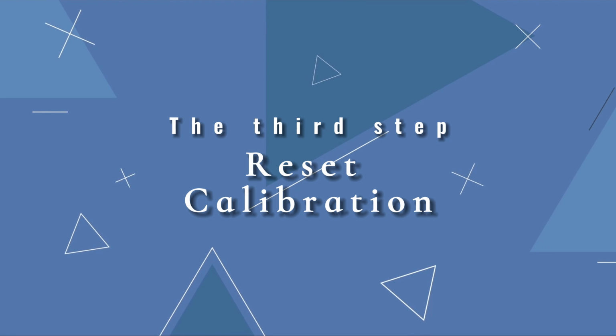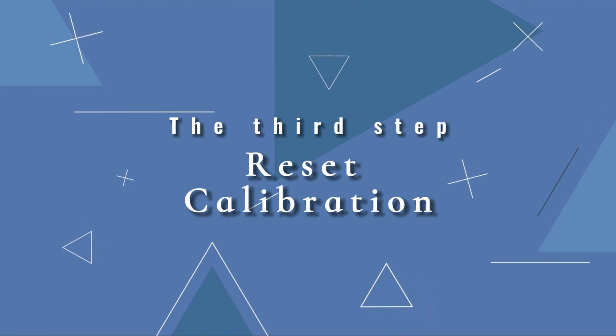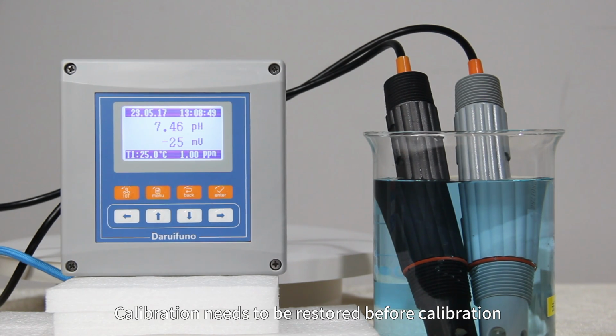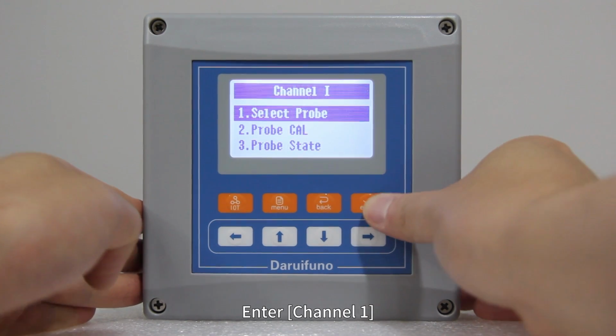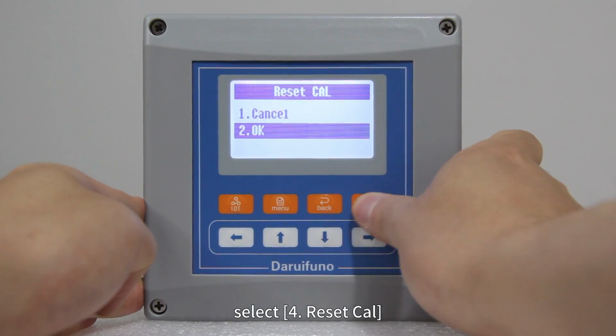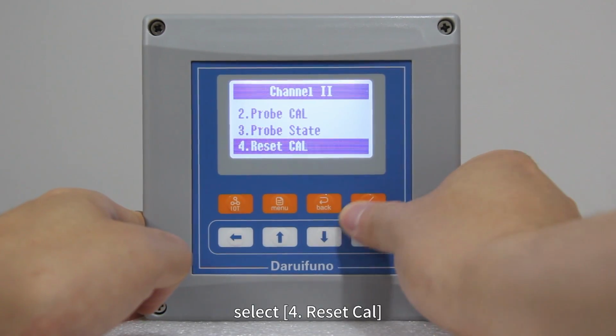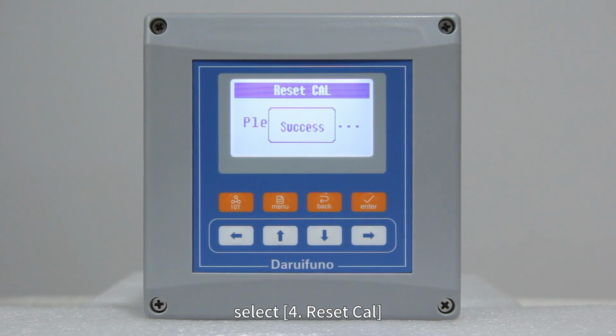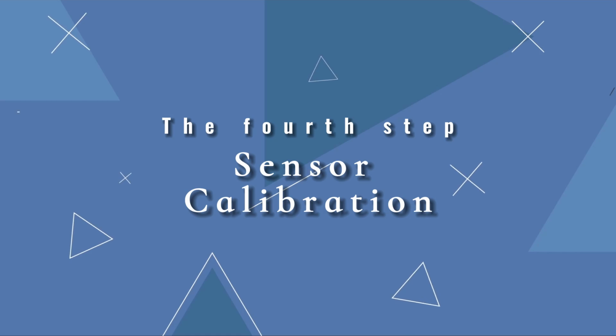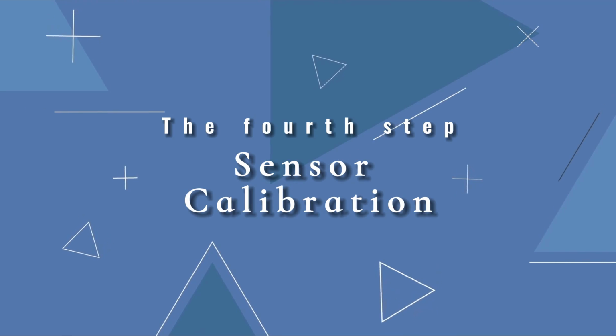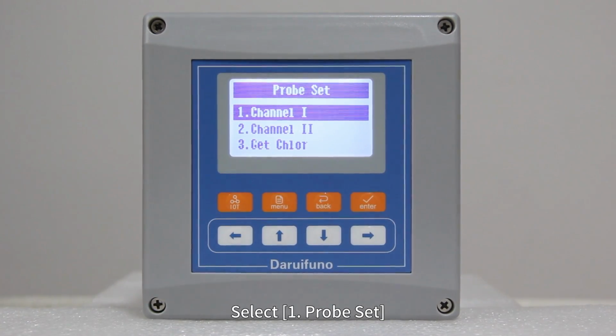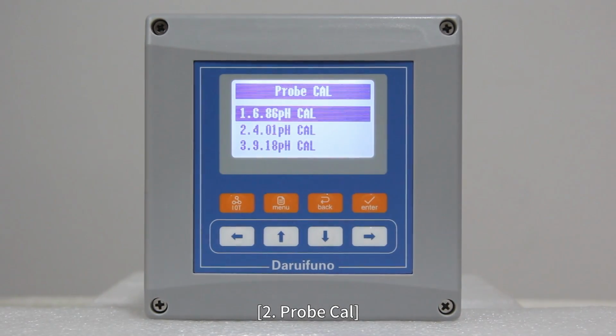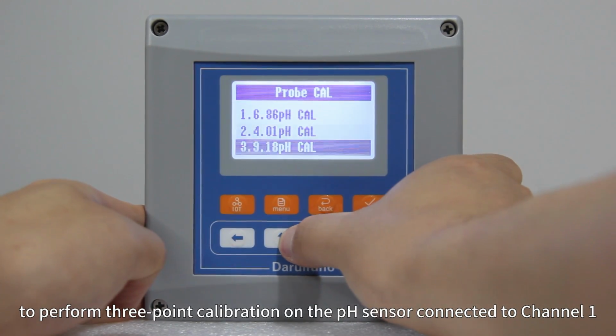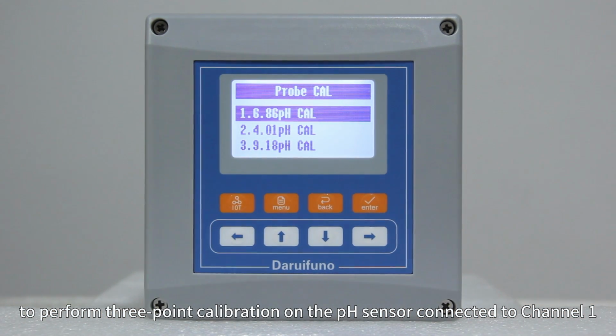The third step, reset calibration. Calibration needs to be restored before calibration. Enter Channel 1. Select Fourth, Reset Cal, and confirm. Enter Channel 2. Select Fourth, Reset Cal, and confirm. The fourth step, sensor calibration. Select First Probe Set, First Channel 1. Second, Probe Cal. To perform 3-point calibration on the pH sensor connected to Channel 1.